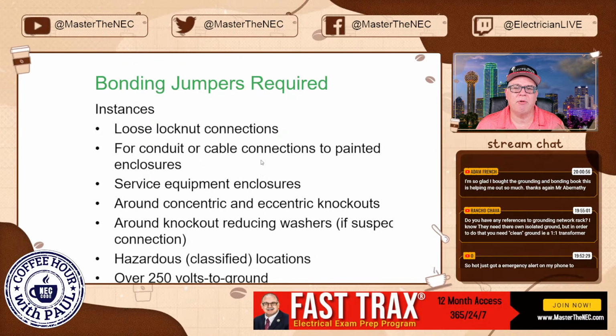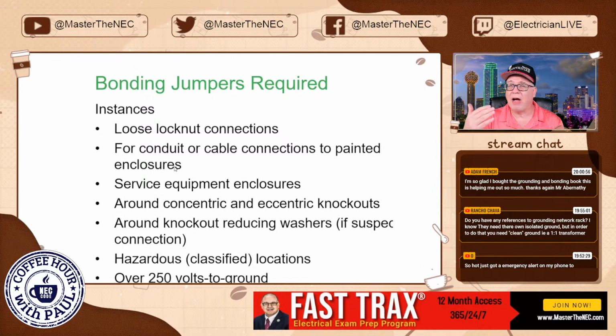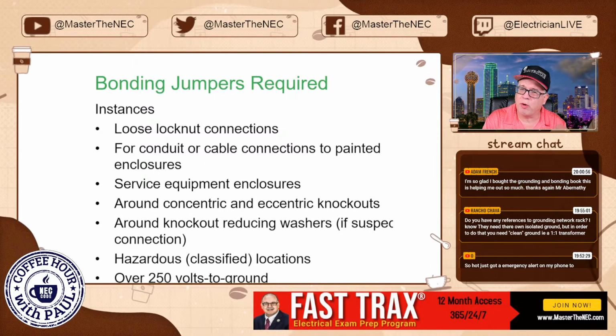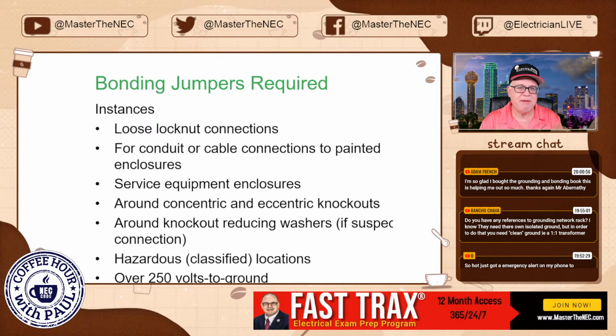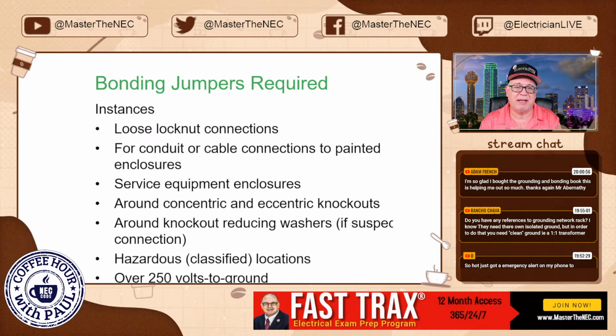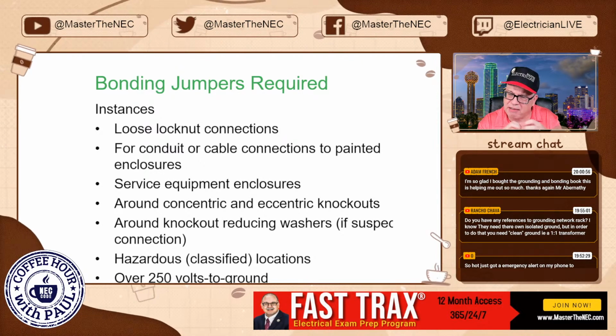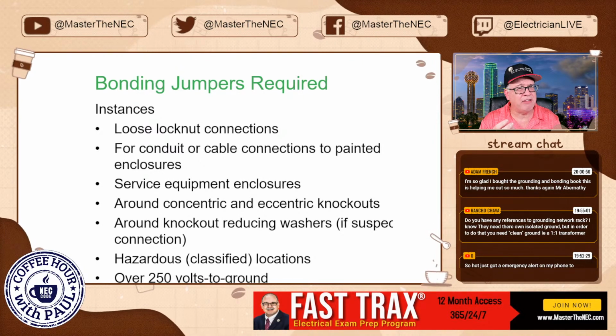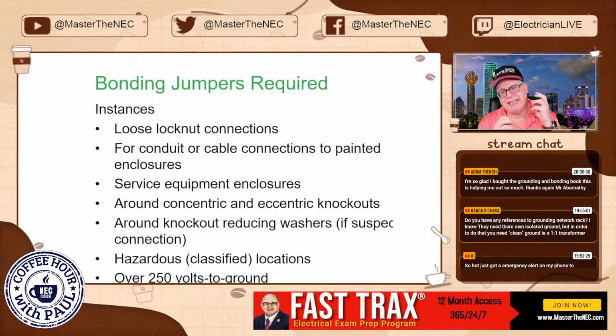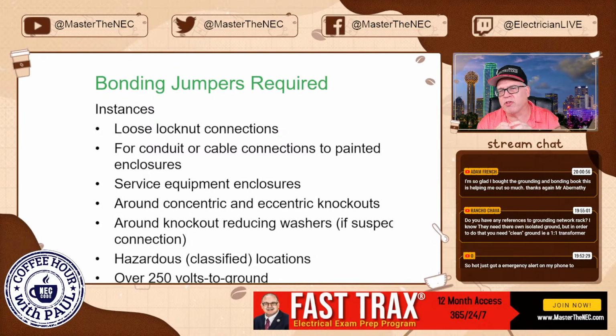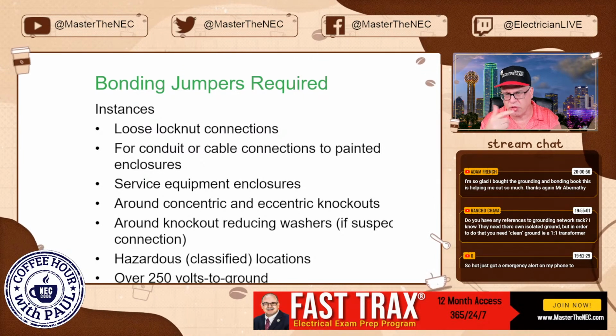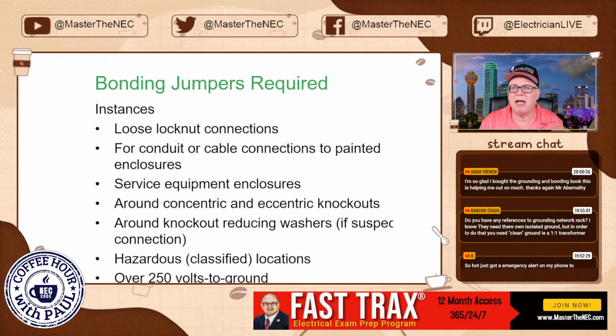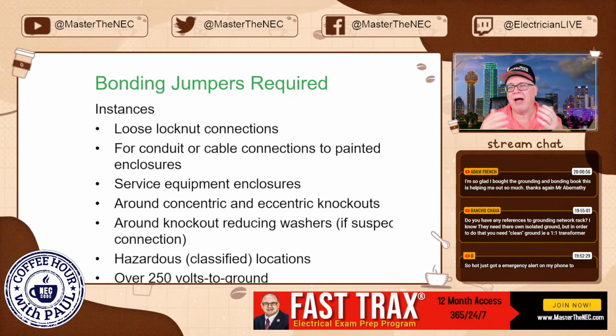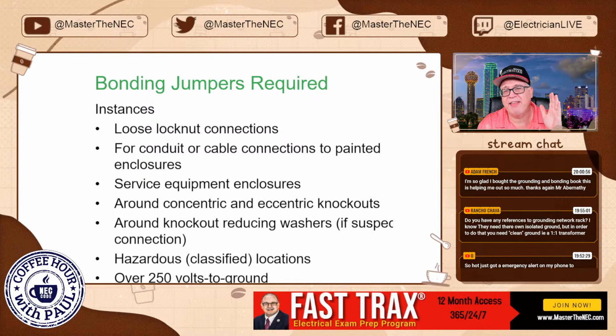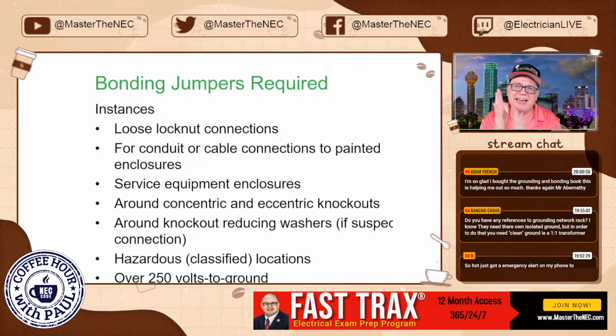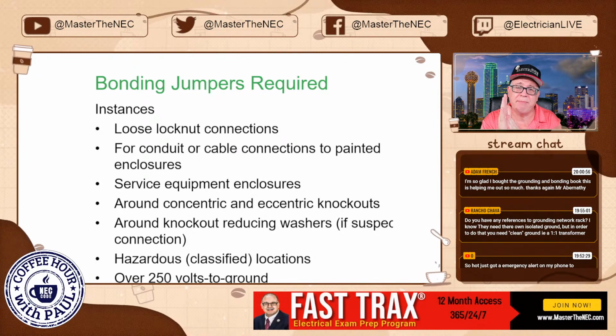For conduit or cable connections to painted enclosures. So I might have a raceway that's making connection to a painted enclosure, and maybe for some reason, based on where it's located or what the application may be, that I cannot bond that raceway, especially if I'm using that raceway as an equipment ground, then I need to make the connection over from the bus over to that conduit or cable fitting as it comes through, the threaded portion. So I need to maybe put a bonding bushing on there and make that connection. So I need a bonding jumper in order to ensure the continuity of that connection, because I'm not going to rely on that connection to the actual painted cabinet or enclosure.